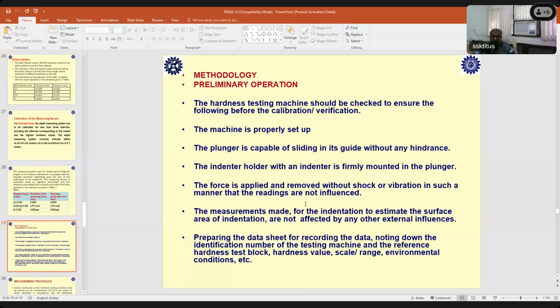These are the preliminary operations one has to take into account whenever we are making the hardness measurement or hardness calibration, because even that can make a lot of variation in the value. Okay, so that is why the indenter holder with the indenter is firmly mounted. This is another thing, because sometimes we keep changing the indenter. For hardness scales, I told you, we have to use a diamond indenter for certain scales and a ball indenter for certain scales. So the plunger has the provision to change the indenter. Whenever you remove one indenter and mount another, it has to be properly fixed. There shouldn't be any loose fitting in the system.